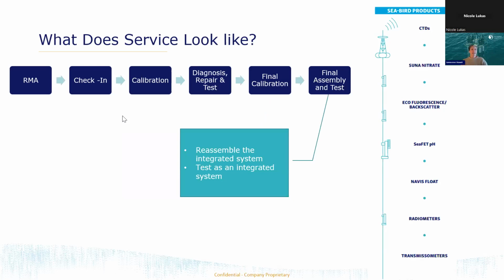The last step, depending on the equipment, is often reassembling systems back into their final configuration. So the individual sensors have been repaired, diagnosed, and recalibrated, and now it's time to bring the whole system back together and test it as the integrated system that you actually use.